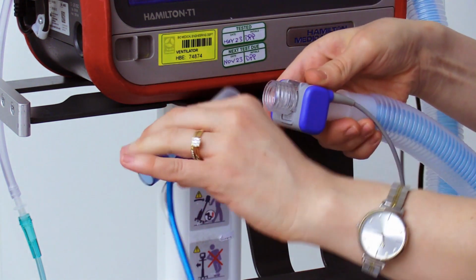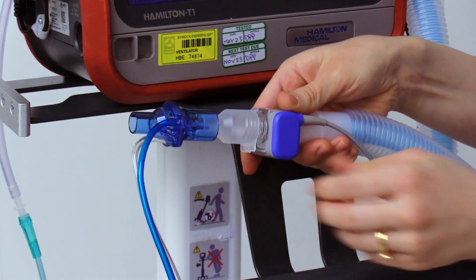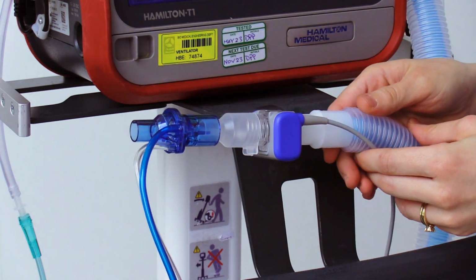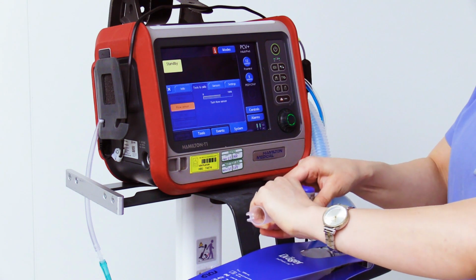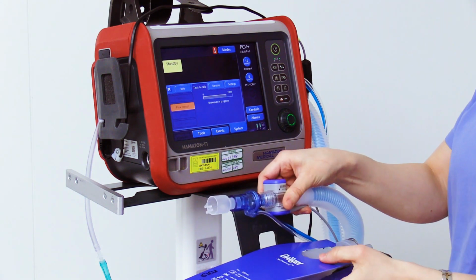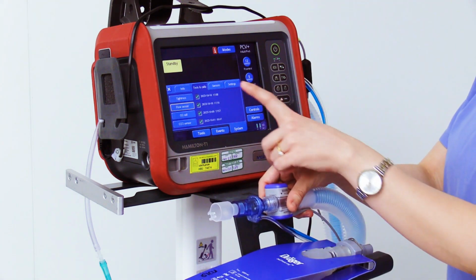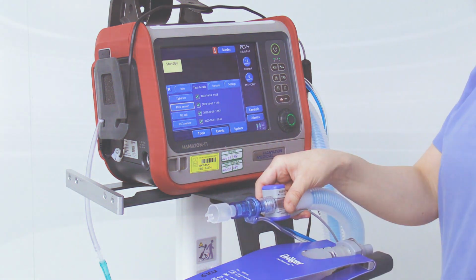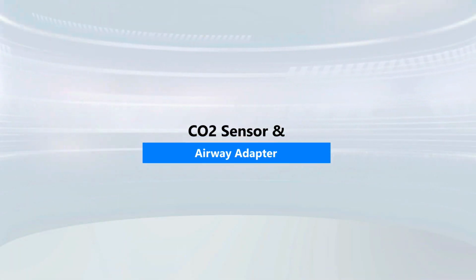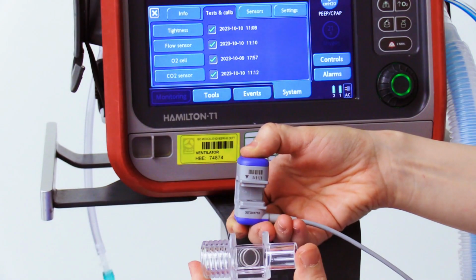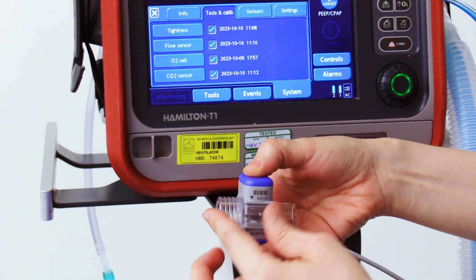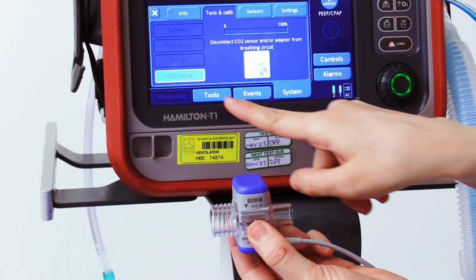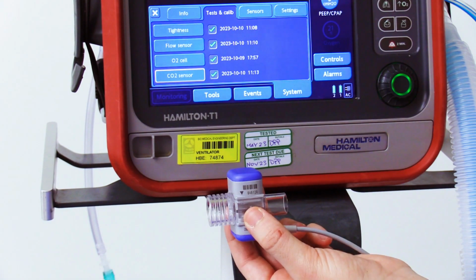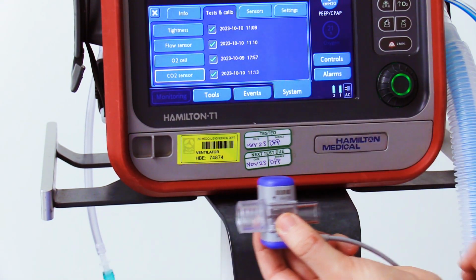Flip the flow sensor around and wait. Finally, return the flow sensor to its initial position. The green checkmark indicates that the flow sensor is calibrated. The CO2 sensor is already calibrated before the ventilator leaves the factory. You only need to calibrate the airway adapter. Press CO2 sensor and follow the instructions. The green checkmark indicates that the CO2 sensor is calibrated.